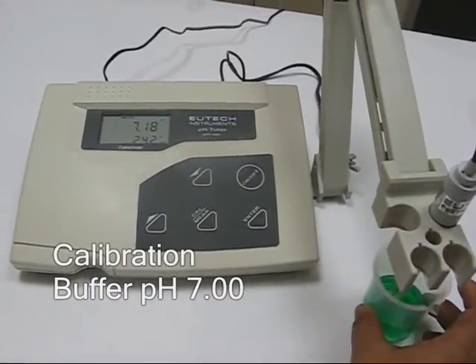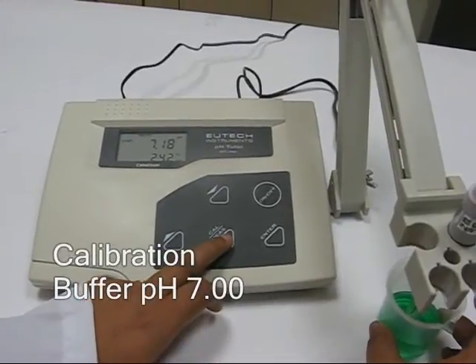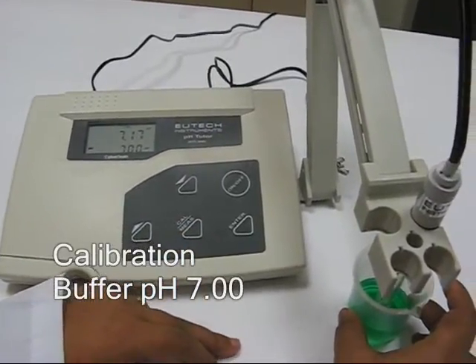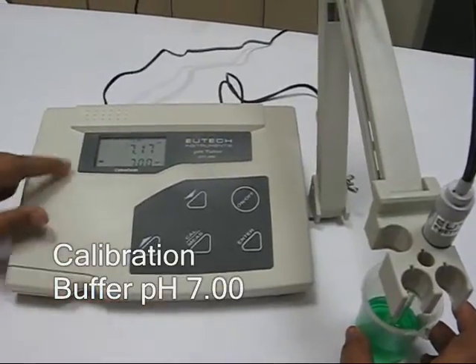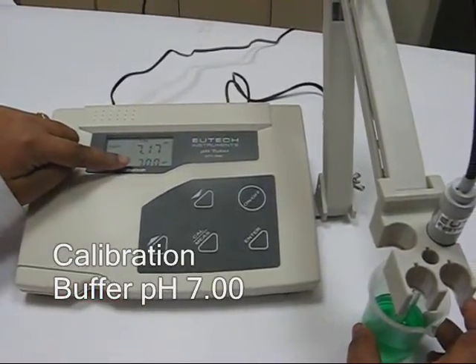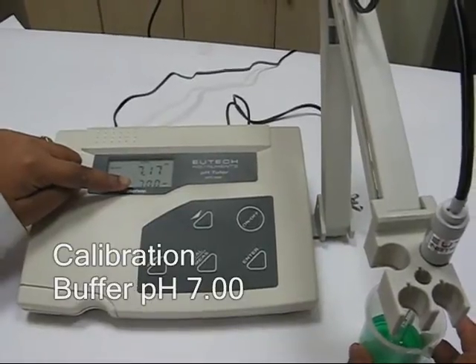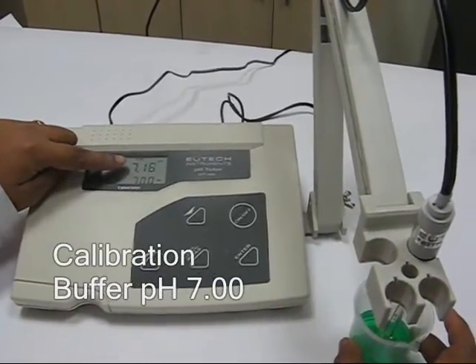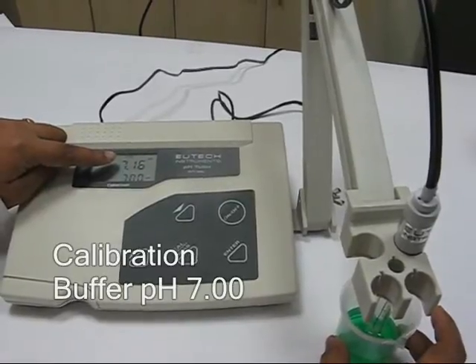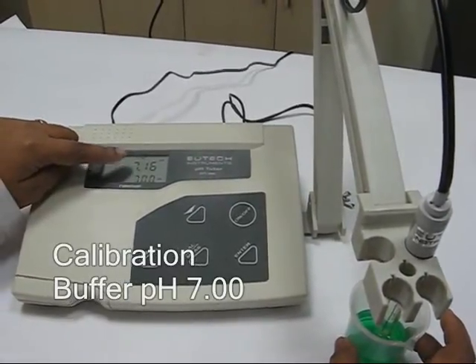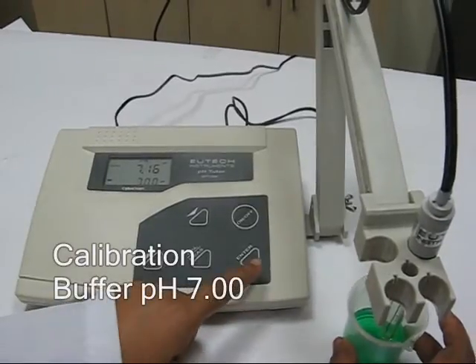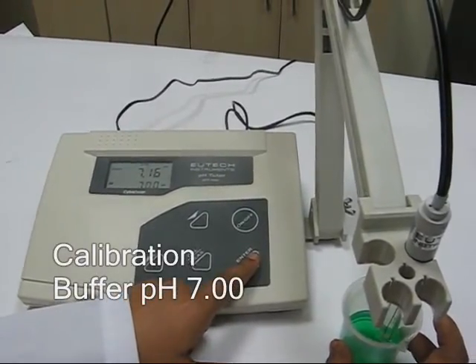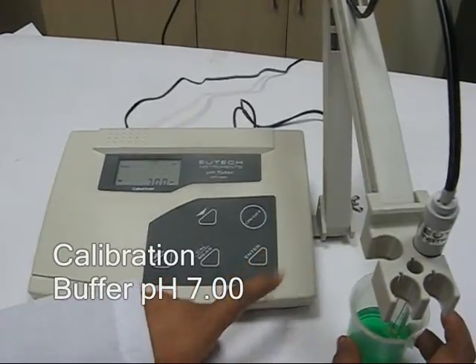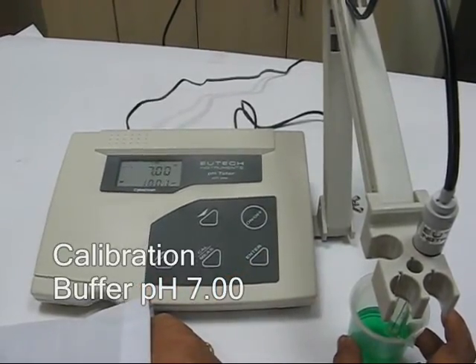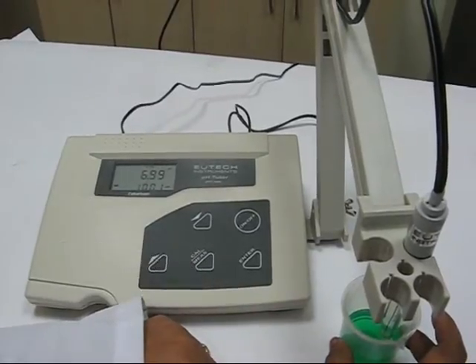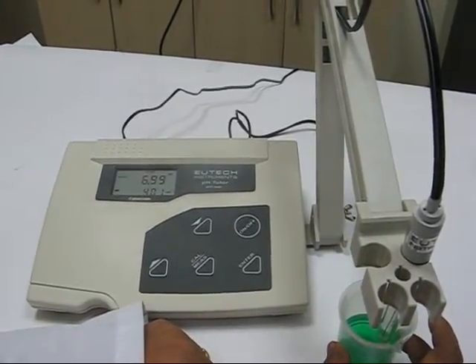and hit the cal key to get into the calibration mode. You will notice that there are two displays. The lower one tells you what the standard is, and the upper display makes the actual measurement. Now, once the reading is stable, you can press the enter key to confirm this cal point. Let's press the enter key. It's confirmed. Now the unit is looking for the second buffer.